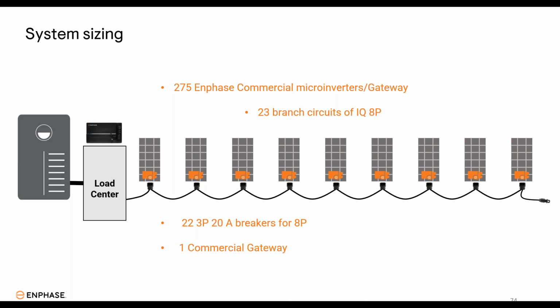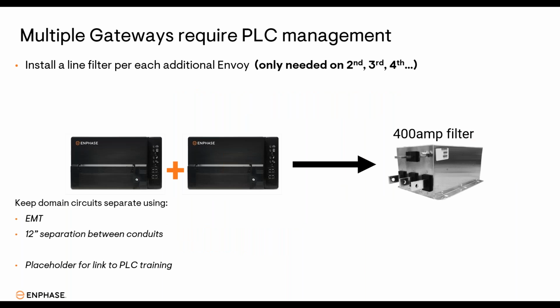If you're designing a project larger than that, it's not an issue. We can still design and build projects larger than 275 commercial microinverters. We just have to add a line filter. With power line communications at the micros being directly through the AC circuits, if you're building a larger site with multiple gateways, you'll need to add line filters to prevent interference or crosstalk over the separate domains. So essentially, for every additional gateway, you'll need to add a line filter for each one.